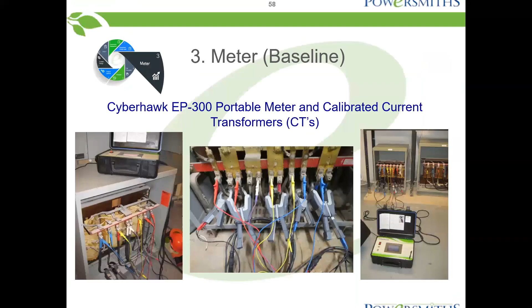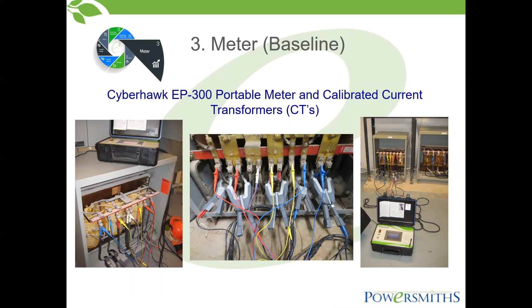We're measuring the primary and secondary side of the transformer simultaneously, so we can look at the real-time losses coming across it. The accuracy is 0.2% on the particular transformer. All of our meters are calibrated to the CTs, because there's always a bit of hysteresis, a little calibration between every CT and the meter.